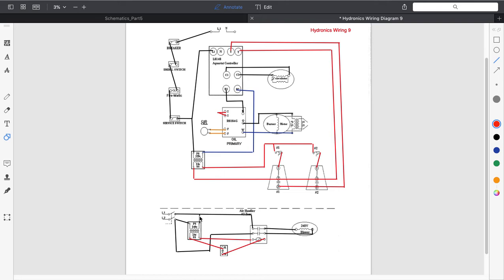So again, sequence of operation: either zone 1 or 2 calls for heat, opens the appropriate zone valve. When the zone valve is open, pins 2 and 3 have connectivity. It's an end switch that closes, operates TT on the aquastat. Aquastat allows the burner to come on. We have flame. CAD cell senses flame. As the water heats up, the pipe clamp thermostat on the air handler will close and turn on the blower motor to move warm air around the space through ductwork. You see this a lot on systems that have a separate air handler for air conditioning, but also have a hot water coil in it.